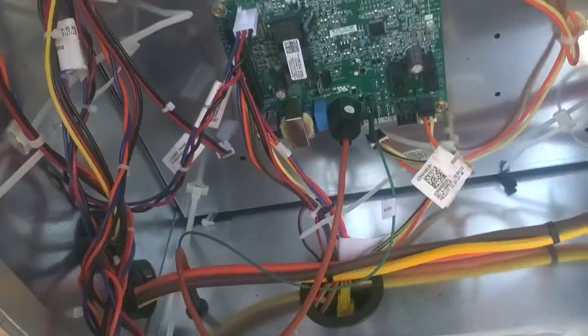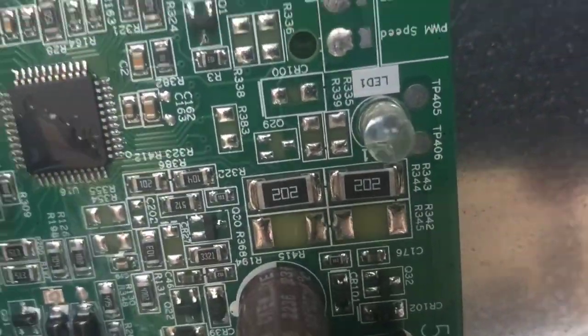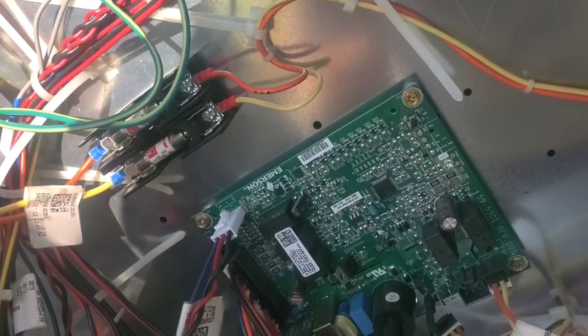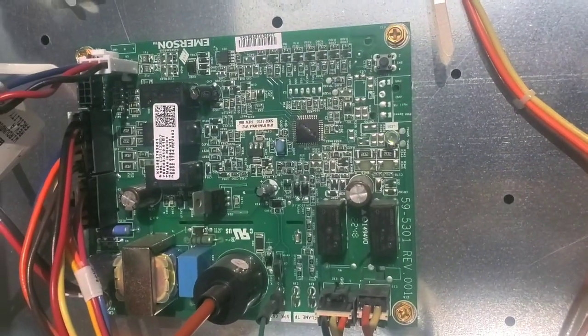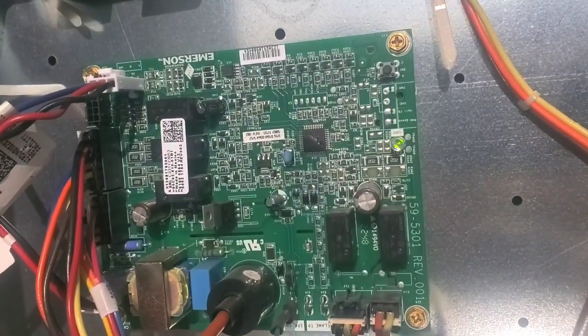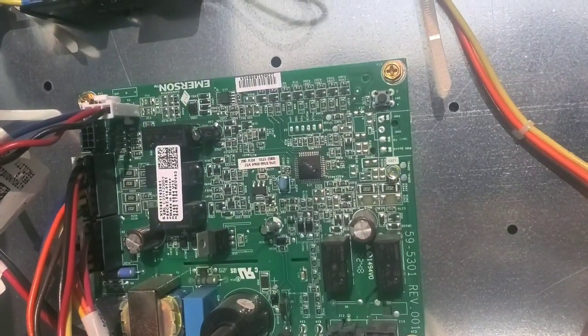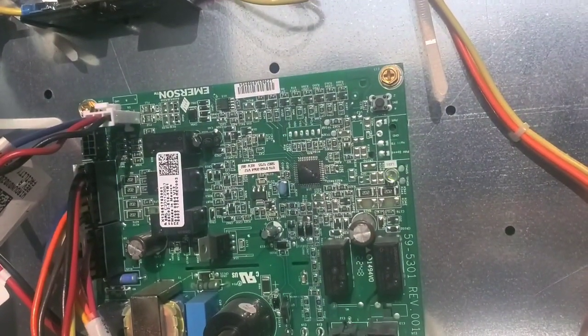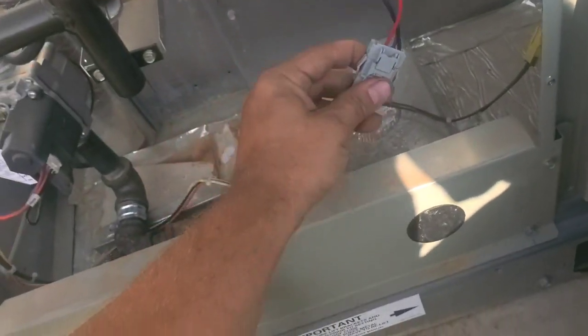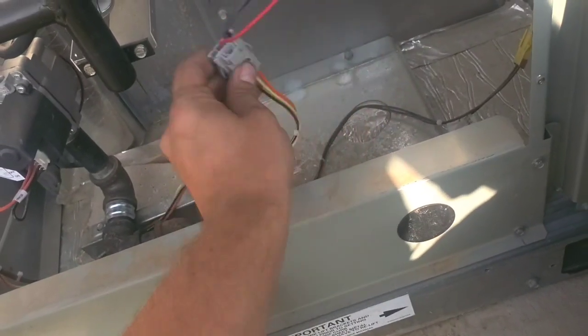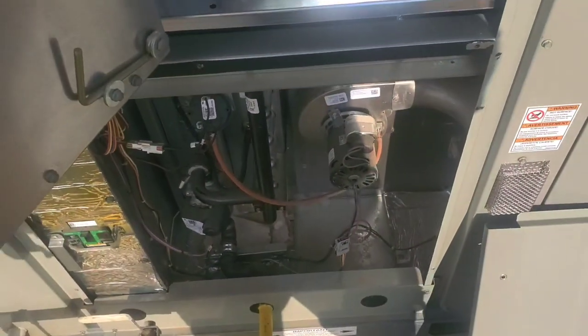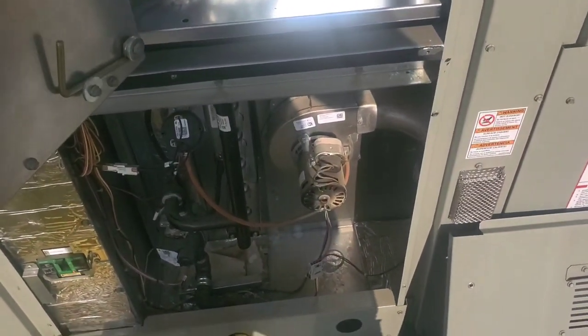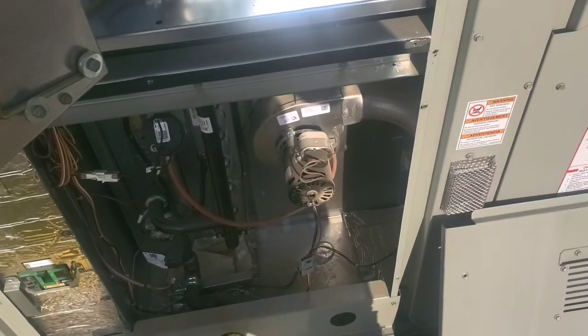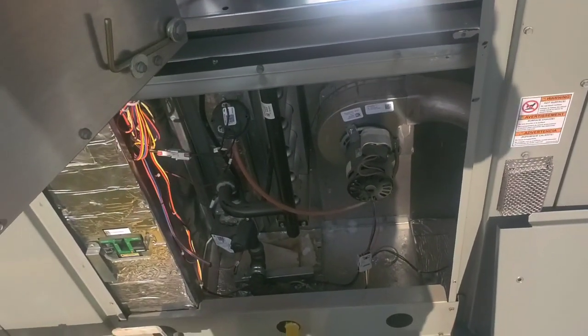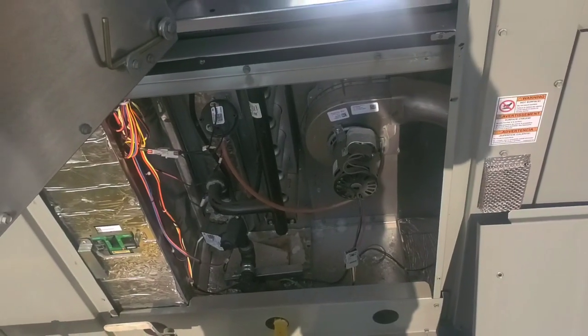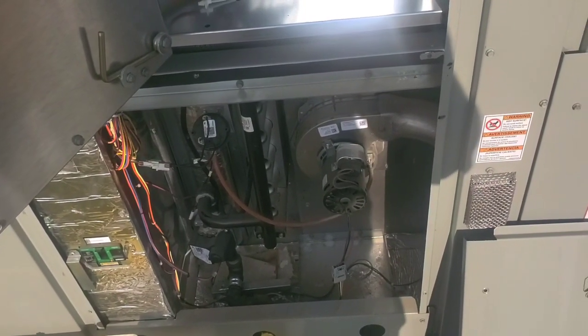Disconnect 24 volts from the heat board. Little LED go out. Put it back. Let's let the board go through its little sequence of 95 relay clicks. Hey, look, and I can move it around all I want. It doesn't turn off. So problem solved, but that's fucking pathetic that I had to do that. Both of these units ship right from the factory with obvious loose connections. And this ain't just an isolated case. This happens all the time. What the fuck is going on with Trane quality control right now?